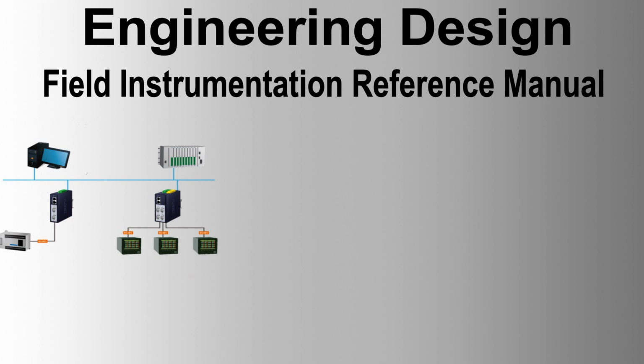Local panels and cubicles. Local panels should be avoided unless approved and must be made of materials and paint systems suitable for the intended location. Instruments in local panels should be mounted at eye level, protected from steam outlets and water. Process fluids should not have direct connections with enclosed instrument panels.